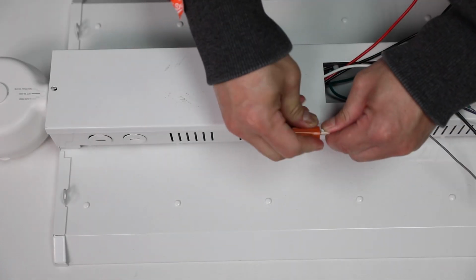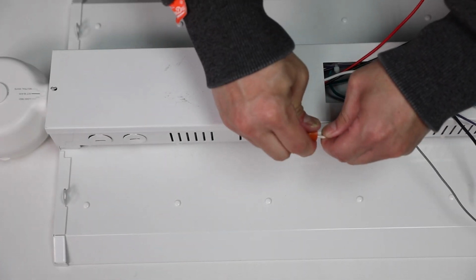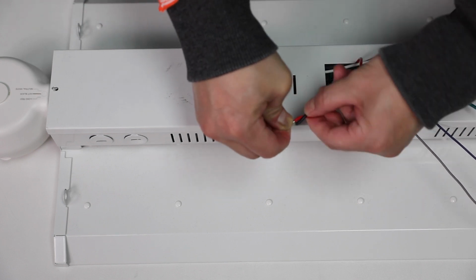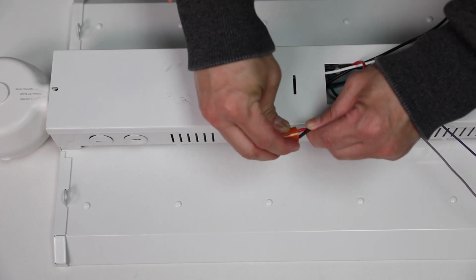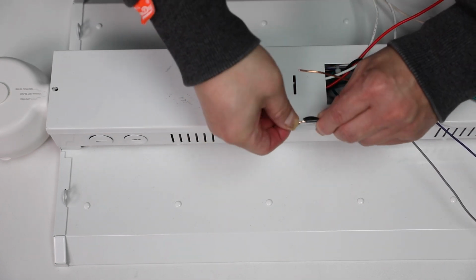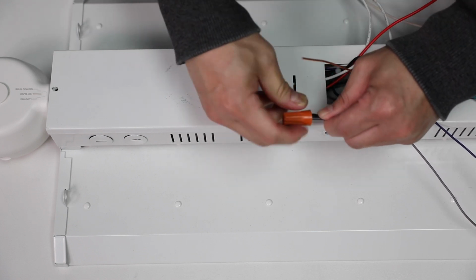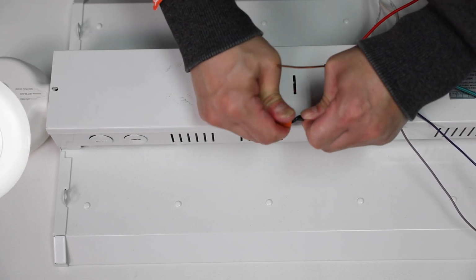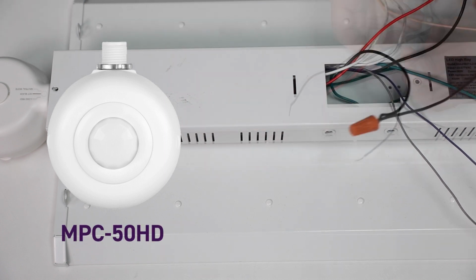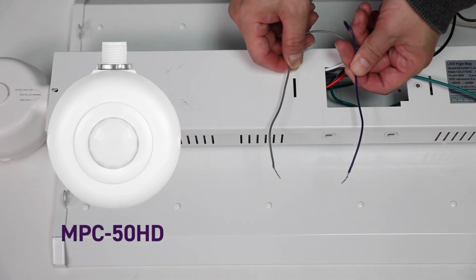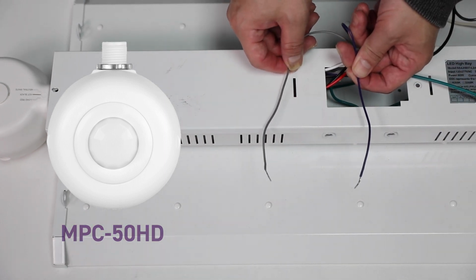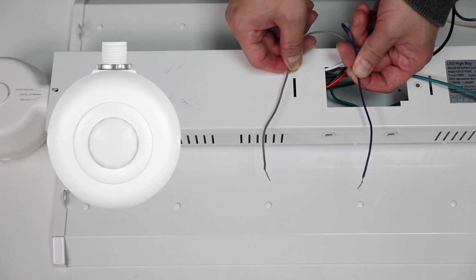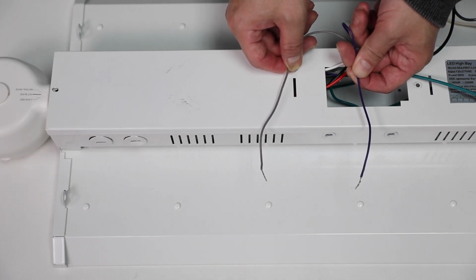Use wire nuts to connect all the neutral wires together. Connect the red wire from the sensor to the black wire on the light fixture, and connect the black wire from the sensor to the hot wire from the line-in. If you are connecting the MPC-50HD to a dimmable ballast or LED driver, connect the 0 to 10 volt low voltage wires, the gray and purple wires, on the sensor to the terminals as indicated on the ballast or driver.